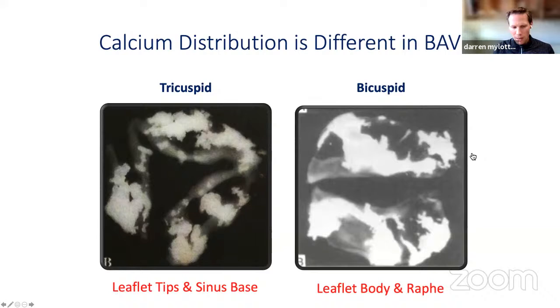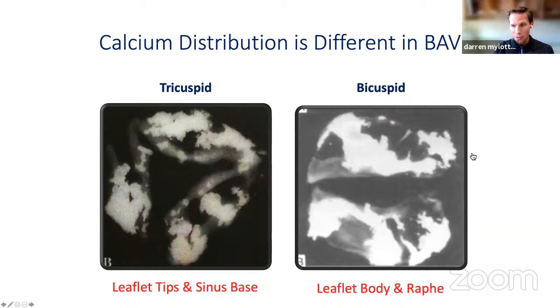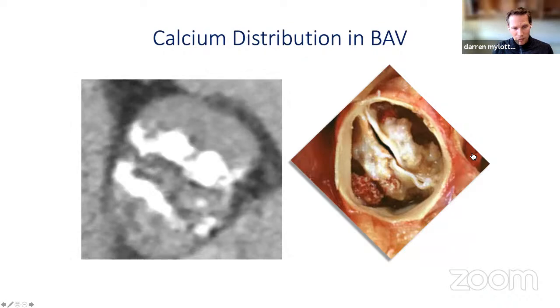In tricuspid aortic valve, calcification is at the leaflet tips and the bases of the sinus. The leaflet tip is not an issue because it folds back into the sinuses, and at the base that's where we size and anchor — so our valve designs are prepared for that. On the other hand, in bicuspid morphology the dense calcification is found not at tips or bases, but right in the body of the leaflet — on average about six to eight millimeters above the level of the annulus — and our devices are not specifically designed for this calcification.